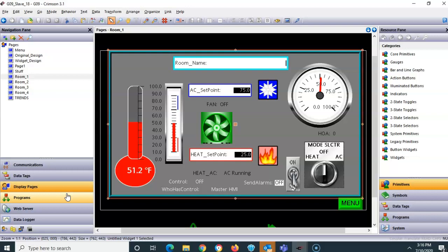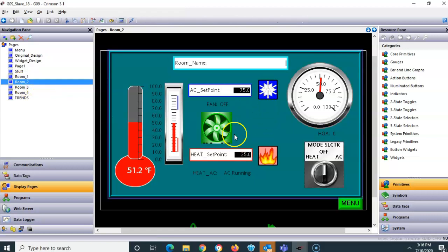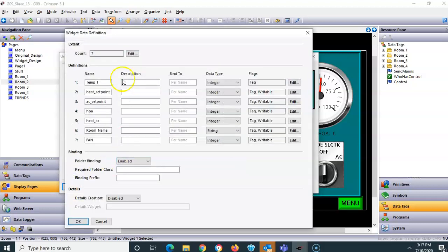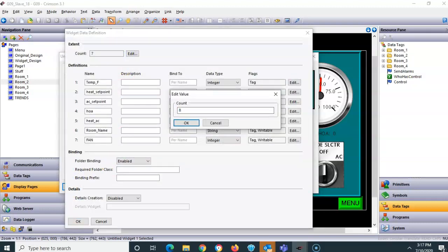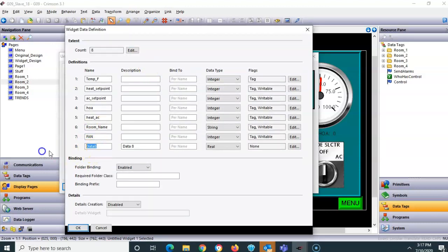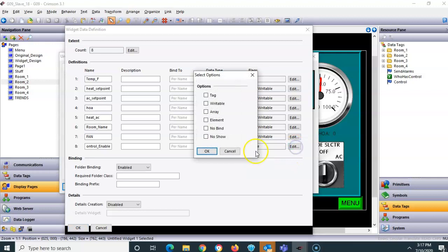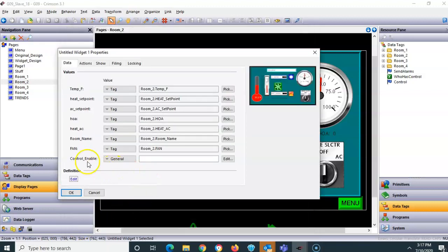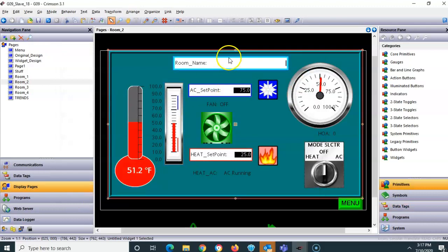I haven't set up room 2 on slave 18 yet, so I'll right-click and go to properties, hit edit, and add widget variable number 8. I'll call it 'control_enable,' make it an integer tag. I'll click okay — that's the widget tag 'control_enable' set up. Now I'll go into each element on this page and apply it.